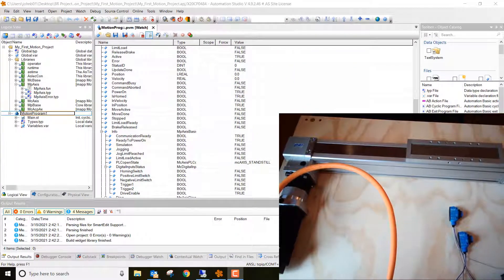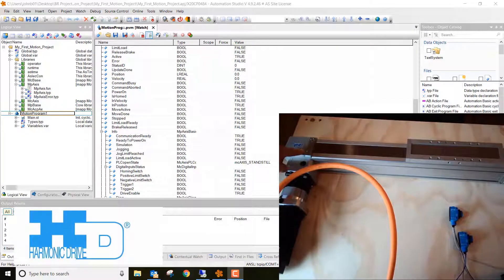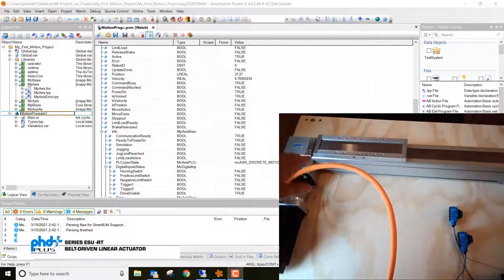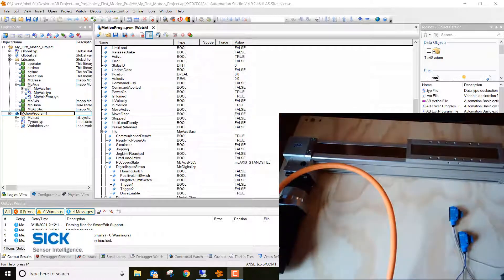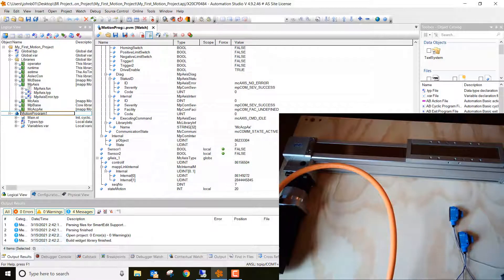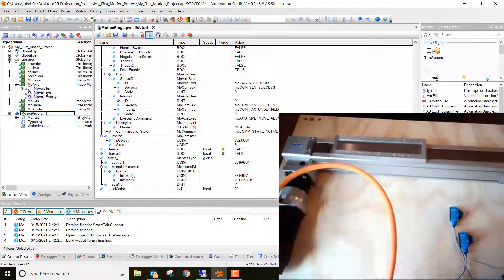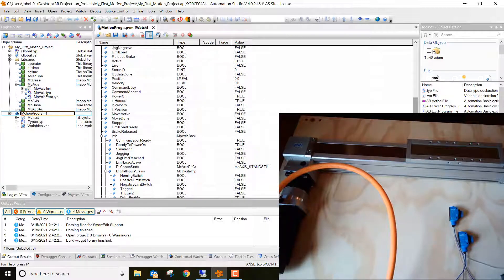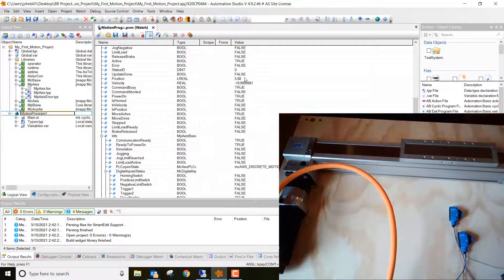Here we are at the workbench. I've got the B&R servo motor hooked up to a harmonic drive gear head, and that's hooked up to the PHD ESU actuator. I also have two SICK sensors as our inputs. If I block the first SICK sensor you'll see it moves one way, and if I block the other SICK sensor it moves the other way. We can monitor this in the watch window in real time — the sensor went true and it moved. Then the next sensor goes true and it moves. We can also see our position: it just went to 37.5, which is what we programmed. Going the other way brings it back to zero.